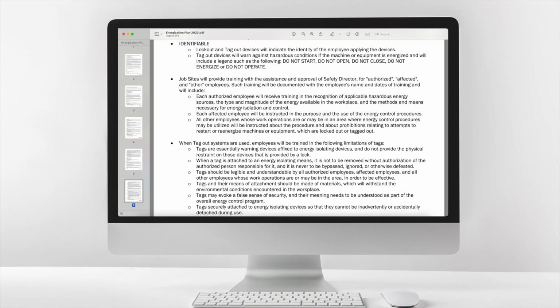When tagout systems are used, employees will be trained in the following limitations of tags. Tags are essentially warning devices affixed to energy-isolating devices, and do not provide the physical restraint on those devices that is provided by a lock. When a tag is attached to an energy isolating means, it is not to be removed without authorization of the authorized person responsible for it, and it is never to be bypassed, ignored, or otherwise defeated. Tags should be legible and understandable by all authorized employees, affected employees, and all other employees whose work operations are or may be in the area, in order to be effective. Tags and their means of attachment should be made of materials which will withstand the environmental conditions encountered in the workplace. Tags may evoke a false sense of security, and their meaning needs to be understood as part of the overall energy control program. Tags must be securely attached to energy isolating devices so that they cannot be inadvertently or accidentally detached during use.